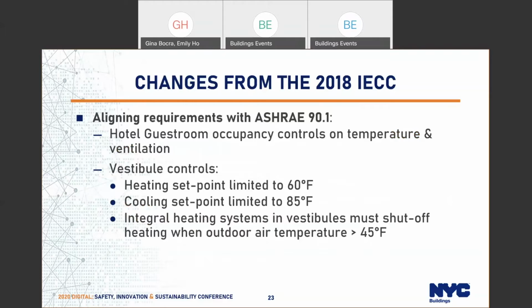If you're familiar with the 2016 code, hotel guest rooms required occupancy controls on the temperature settings, right? So when the room was not occupied, the temperature had to automatically set back within the hotel room. ASHRAE now added a ventilation control, saying that the ventilation had to be shut off when there were no occupants within the hotel room after X amount of time. So that was just alignment with ASHRAE 90.1, taking that language directly over. Also, vestibule heating and cooling controls were brought over from 90.1 into the ECC. So now there's alignment there.